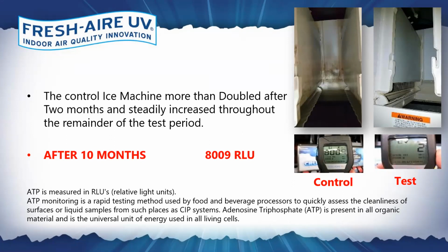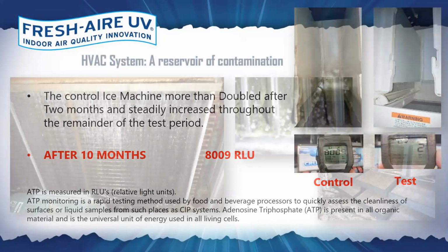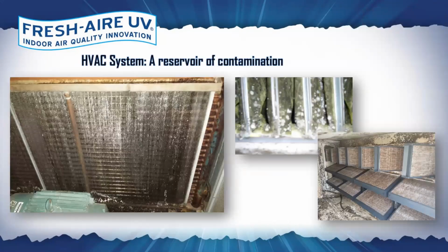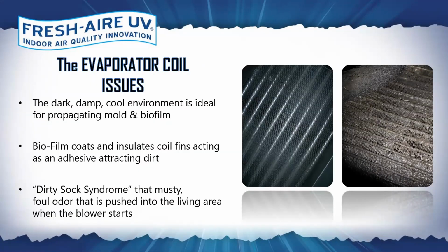So this is indicative of what's happening inside the ice machine, but also what's happening inside the HVAC equipment itself. Now, certainly, we have the HVAC coils that have very tight packed fins. And immediately after commissioning the HVAC equipment, you start getting biofilm. It starts microscopic, it starts insulating the fins of the coil. You start having heat transfer loss. There's static pressure issues because the air has to pass through those fins of the coil that are slowly getting insulated and plugged up by the biofilm. The particles that make it past the filter get embedded on the biofilm, almost like an adhesive. There's wear and tear on the system.